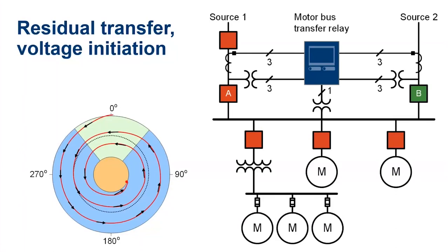And so what would happen in the synchroscope domain is we'll see that the phase starts spinning and the voltage magnitude goes down until the point where it goes below the given threshold. It's important to note here that the slip frequency can be high, can be 35 hertz per second. And so while we are doing a transfer, we decouple from the traditional way of obtaining phasors in such a way that the voltage measurement is not attenuated by tracking frequency.